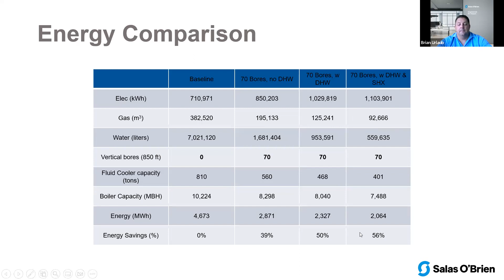Again, with thermal storage. So the last iteration I had on here, we were down to about 2 megawatt in with the 70 bores, domestic hot water, sewage heat recovery. But we're saving a ton of energy overall in those scenarios, over 50% in total energy with geothermal, domestic hot water, and then sewage heat recovery. So again, I mentioned we gave them a lot of other options. They can reduce their ventilation, reduce their domestic hot water load, look at thermal storage, which we did analyze.